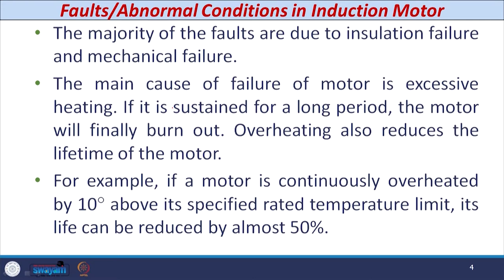The main cause of failure of a motor is because of excessive heating. If this type of heating is sustained by the motor for a longer duration, then the motor will finally burn out. Overheating also reduces the lifetime of the motor. For example, if the motor is continuously overheated 10 degrees above the specified temperature value in the datasheet, its life can be reduced by almost 50%.